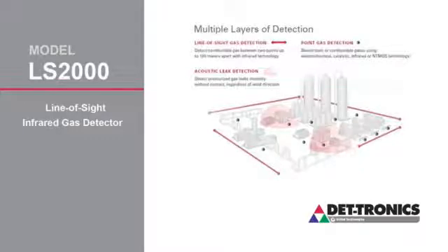And finally, what we're here to talk about today is a line-of-sight detector. Line-of-sight detectors can be separated by over 100 meters. The system consists of transmitter and a receiver, and we can detect the presence of gas anywhere in between those two detection points. These detectors are well suited for monitoring fence lines, perimeters, or large areas in between storage tanks. Each of these gas technology types has an application where it's best suited, and often more than one type of technology is needed to provide the optimal solution.